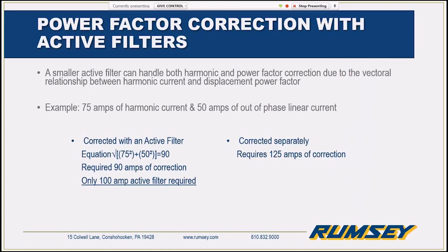Then we talked a little bit about the power factor correction. Because of the vectoral relationship between out-of-phase linear current and harmonic distortion, we're able to do more with less. So with this little example of 75 amps of harmonic current and 50 amps of out-of-phase linear current, if you were to correct for them separately, let's pretend you had 75 amps of passive filter correction on the VFDs and 50 amps worth of power factor correction for the linear drives, you'd have to correct for 125 amps of correction.